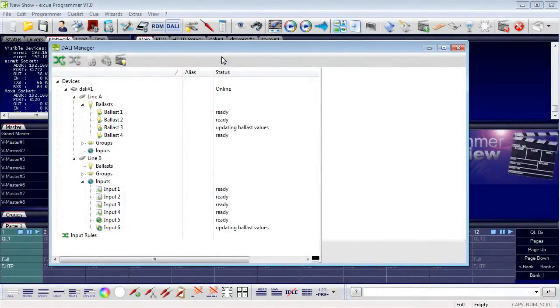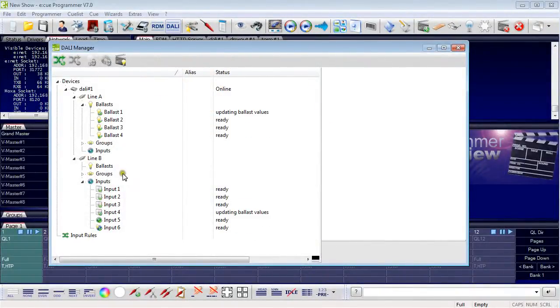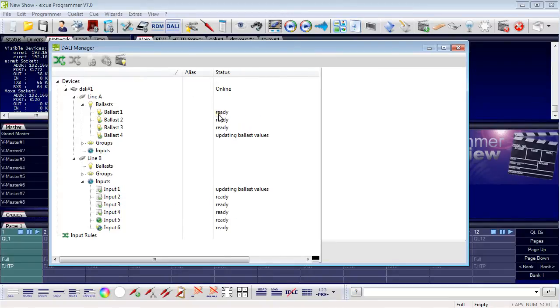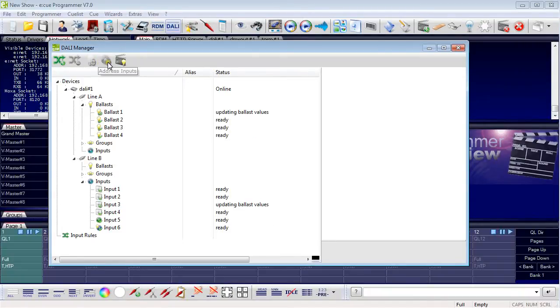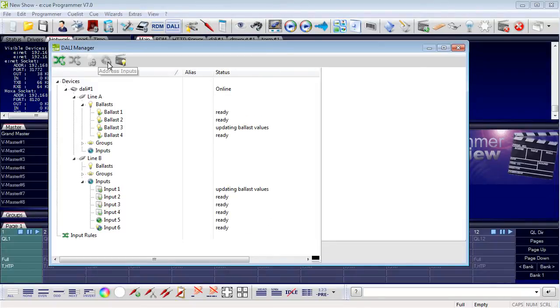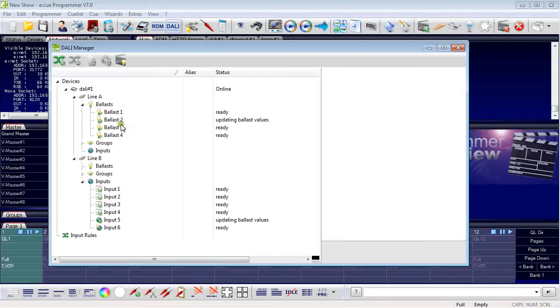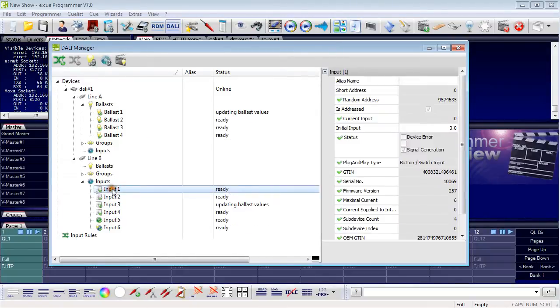The DALI manager is already open and you can see that all devices — ballasts and input devices — have assigned short addresses. To do this, use one icon in the top to address ballasts and the other one to address inputs. We already had this in the video about ballasts. Buttons are sometimes referred to as keys in DALI.